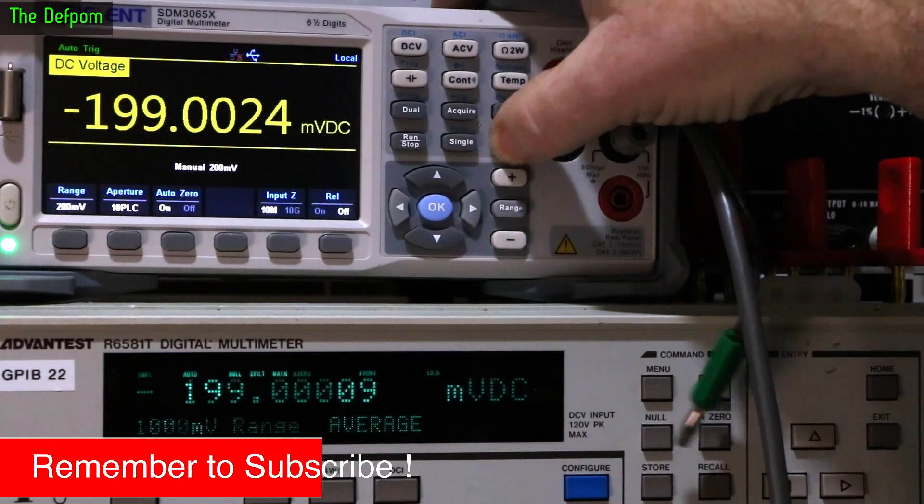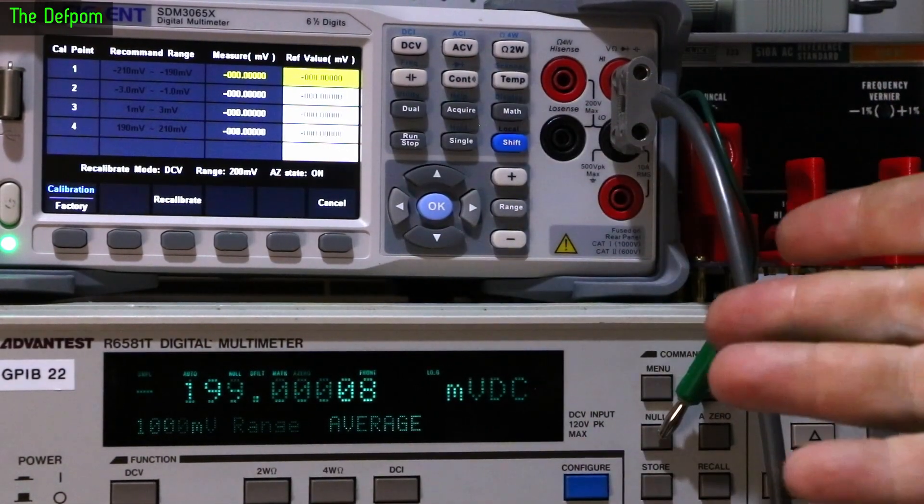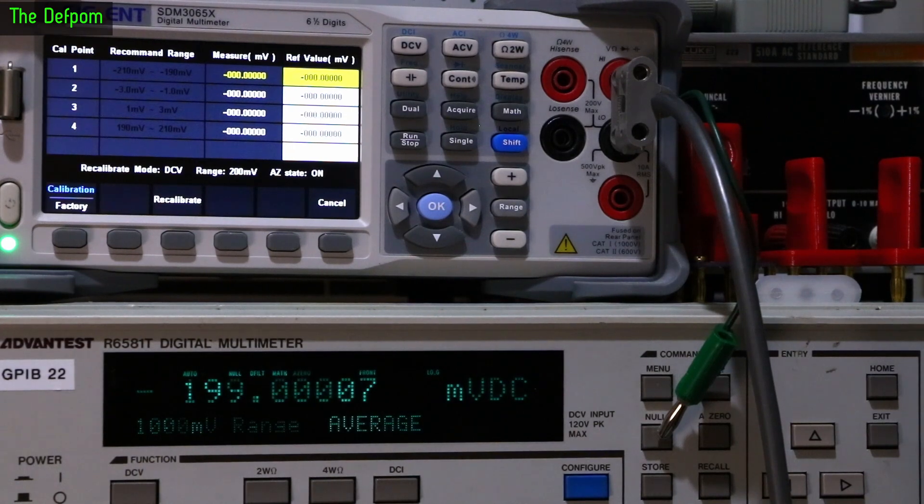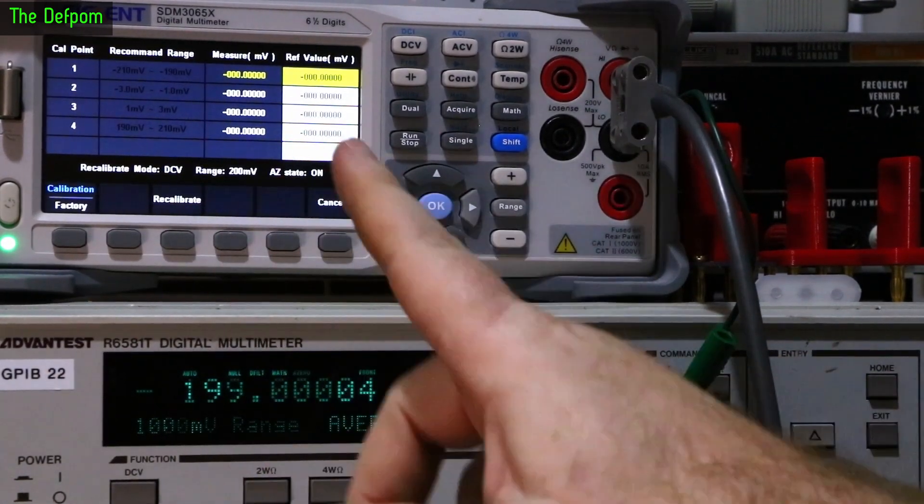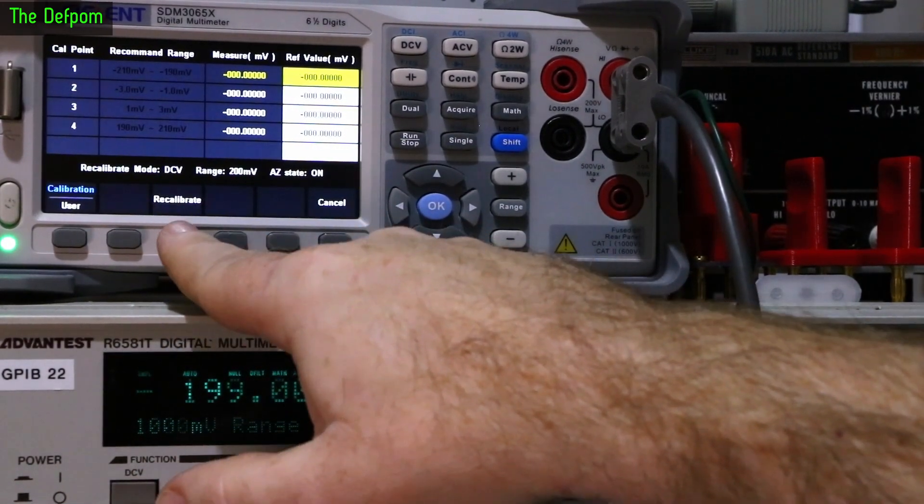I go shift, utility first, system setup, calibration. This is once you've got the newer firmware installed - firmware 3.01.01.12 R1 or newer. Here's the calibration screen for factory calibration. If you want to use user calibration, you come in here to user recalibrate, then push on recalibrate.